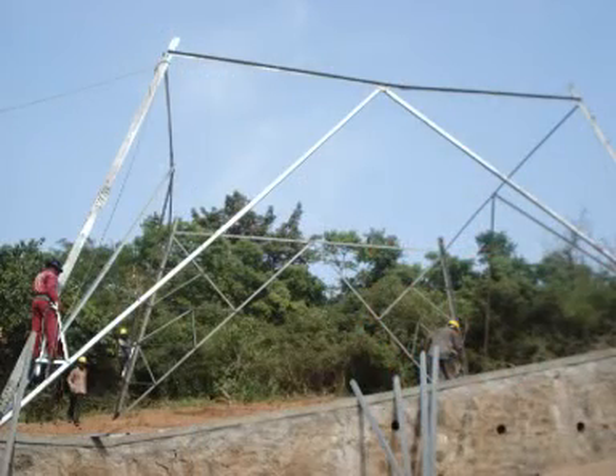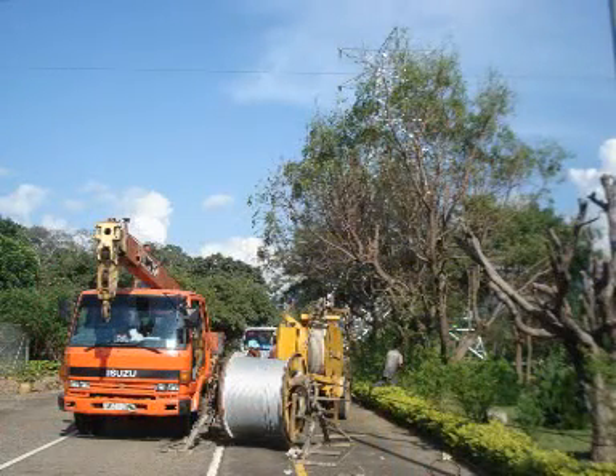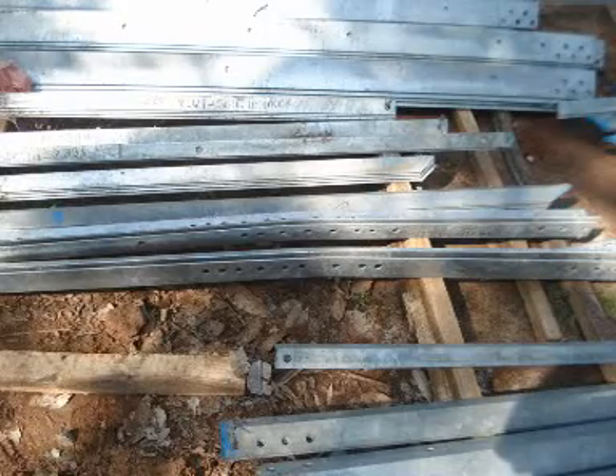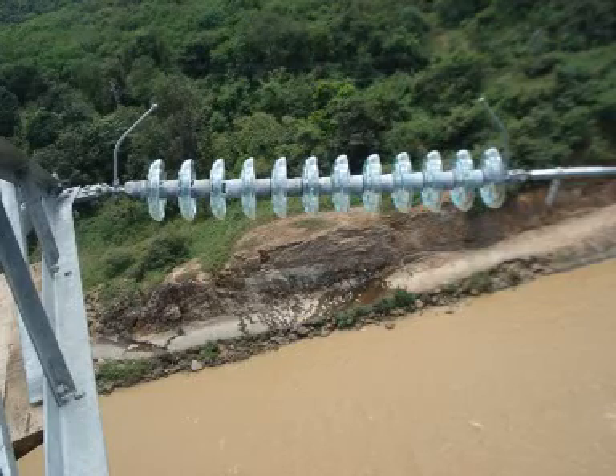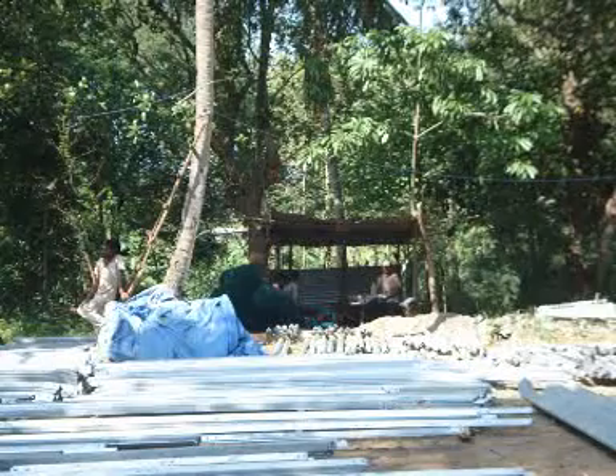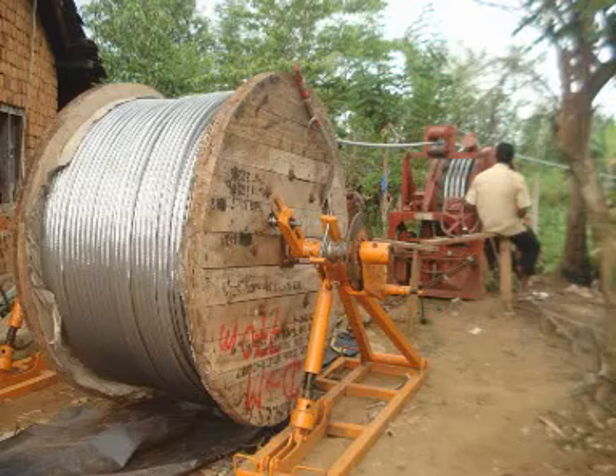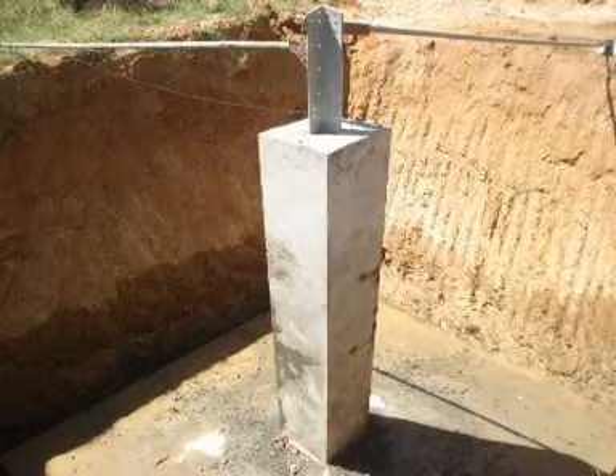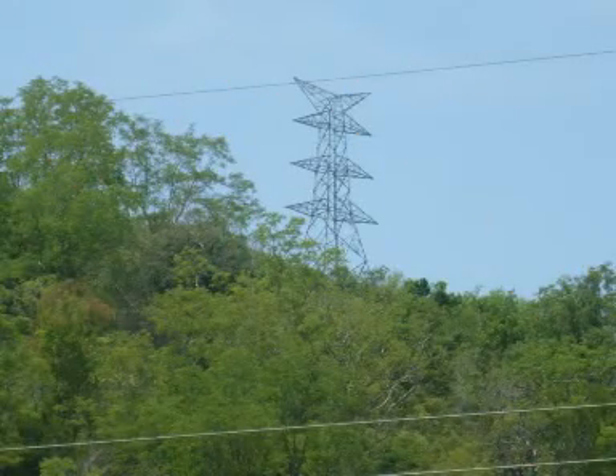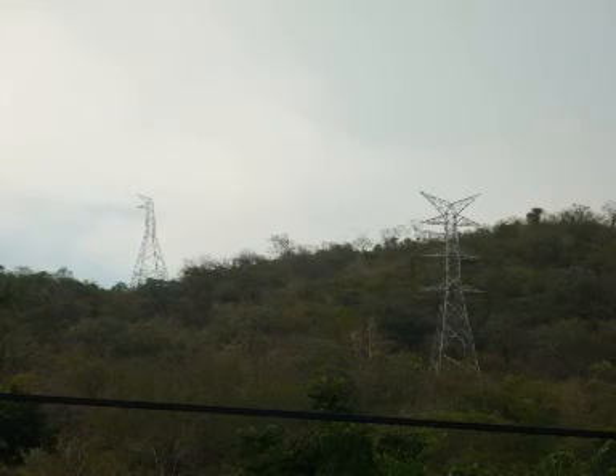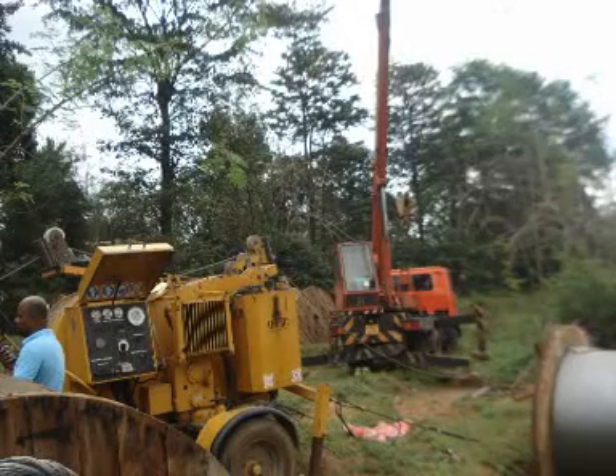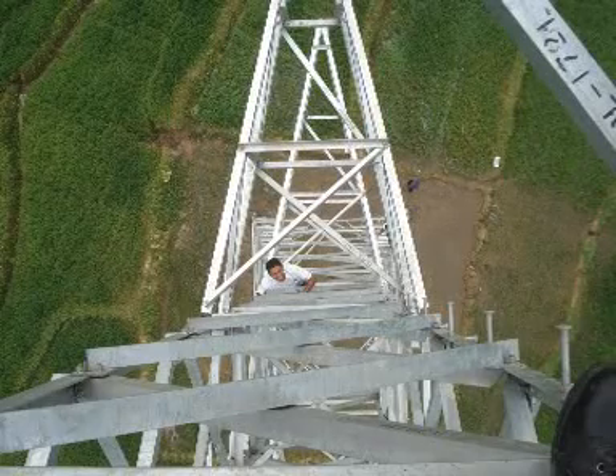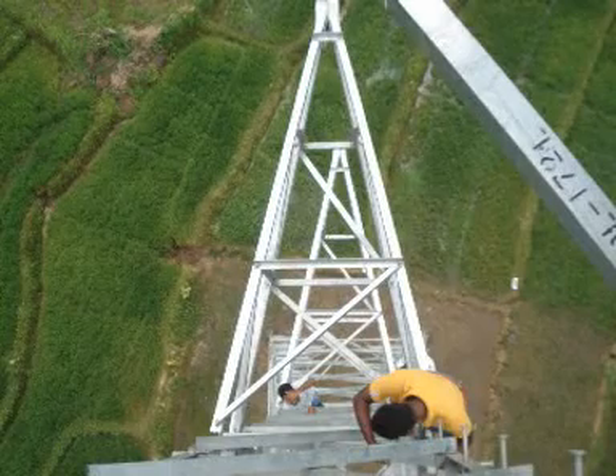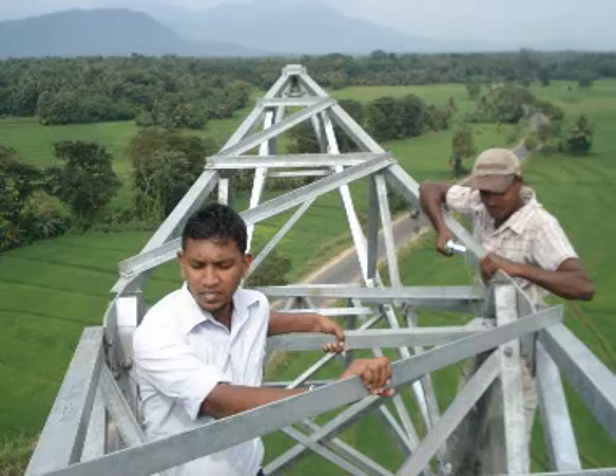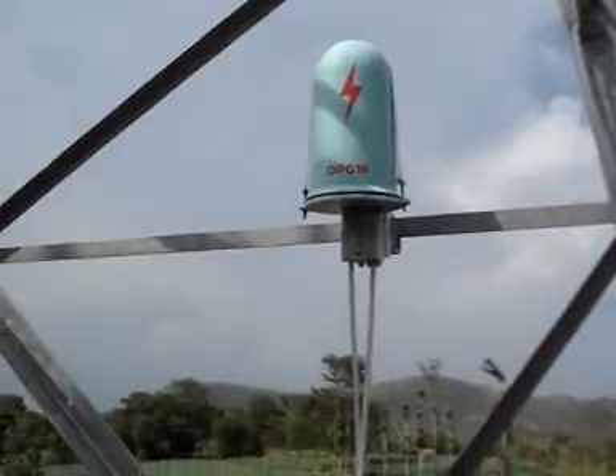Construction work of the line was mainly carried out in different phases, such as construction of foundations, tower erection and stringing of conductors and earth wires. In the meantime, materials were procured through separate tenders, such as tower stubs, tower materials, insulators, hardware and accessories, conductors and earth wires, OPGW and accessories, etc. Tenders were also invited for foundation erection, erection of towers and stringing of conductors. Tower stubs and conductors were procured in Sri Lanka, and tower materials and earth wires were imported from India. Towers were tested in the presence of CEB inspectors.